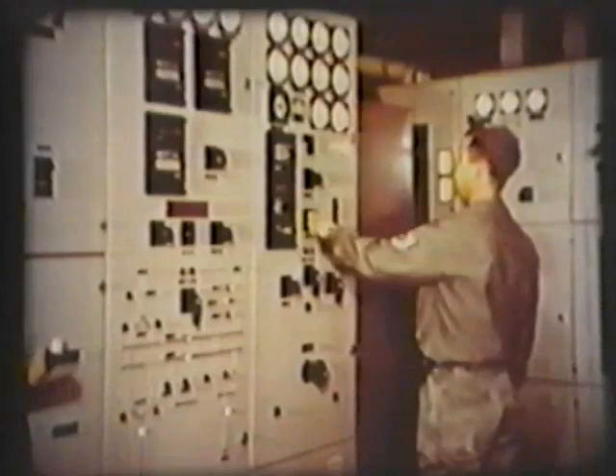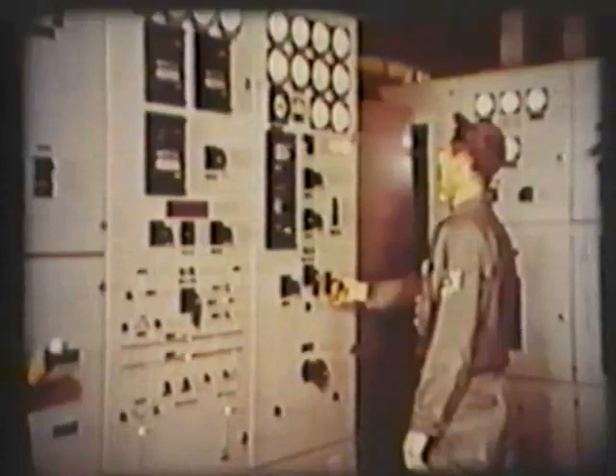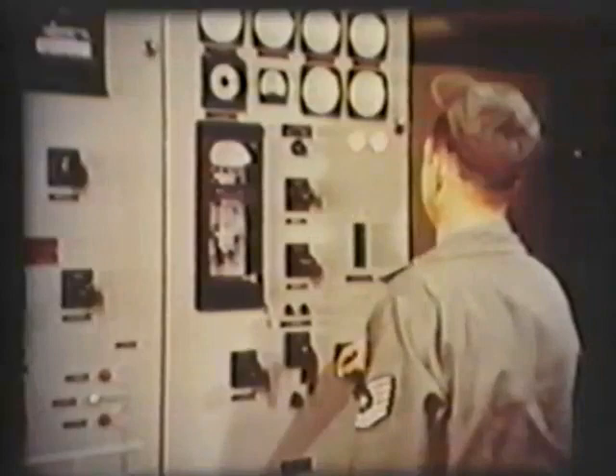The SL-1 was designed to meet the requirements for extended operation without refueling. The reactor was a direct cycle, natural recirculation boiling water system of 3 million watts gross thermal capacity, designed to produce 200 kilowatts of net electricity and 400 kilowatts of net energy in the form of space heat.